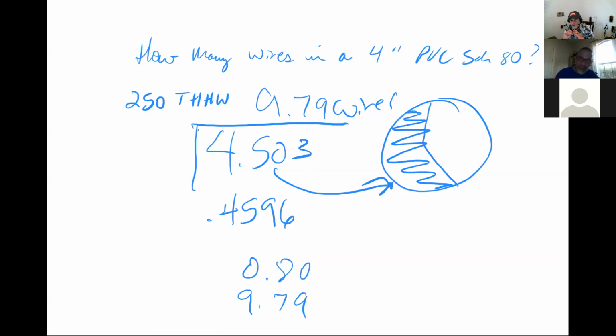We're not allowed to round up until we hit that magic 0.8. So 80% of that wire's got to be in the area I'm allowed to be in, meaning only 20% is allowed in the other area. 21% would be too much. Anything under 0.80, round down. So this rounds down to 9.